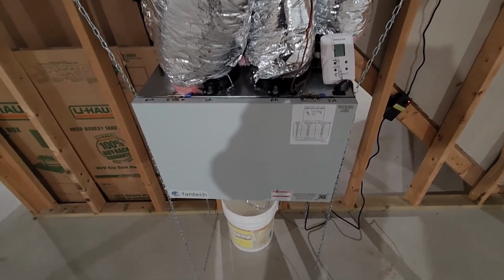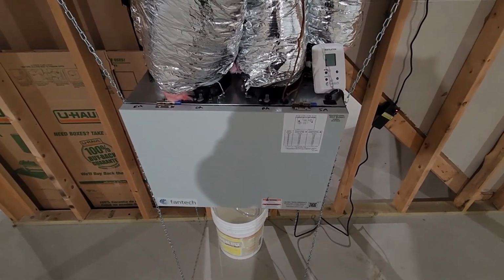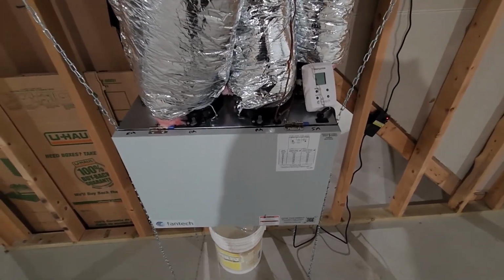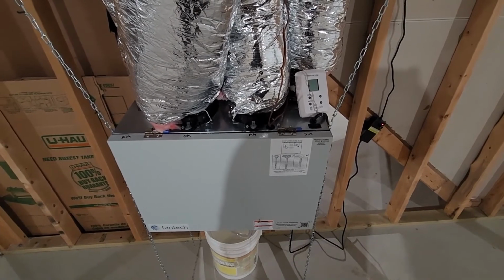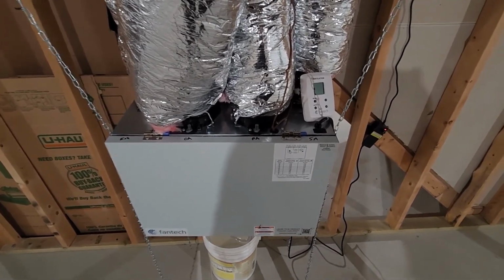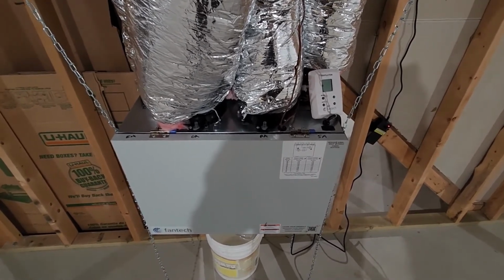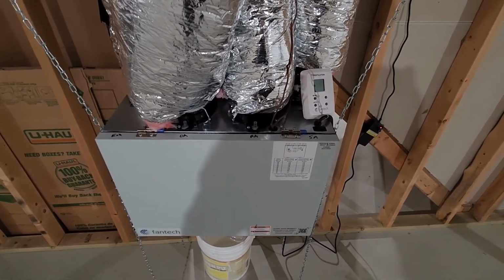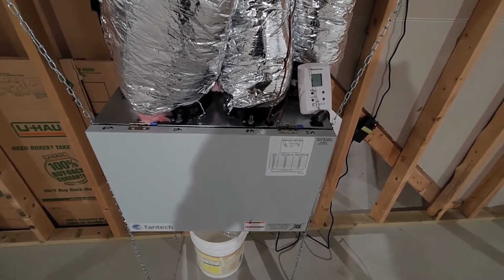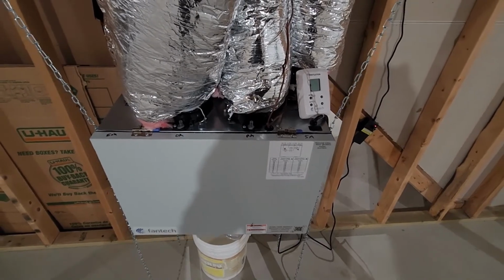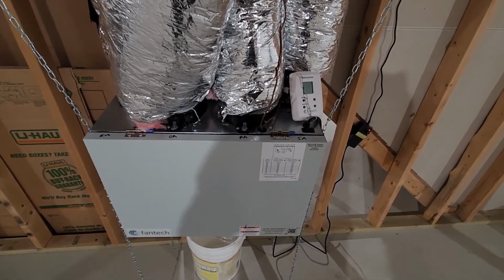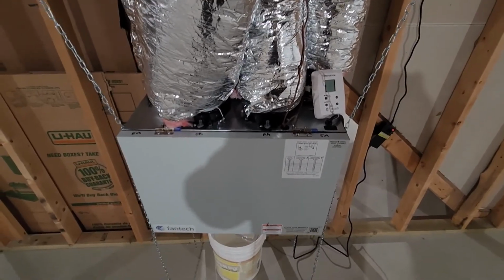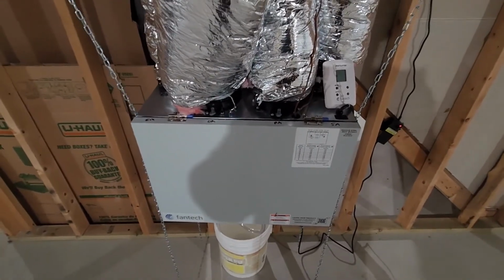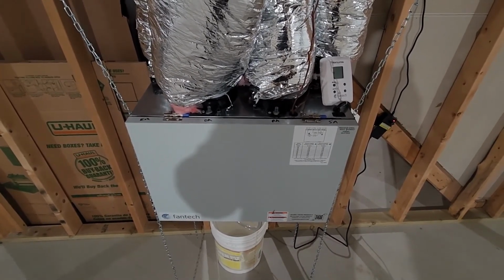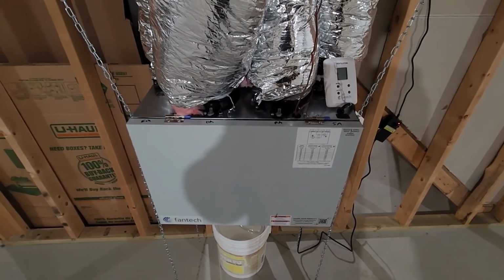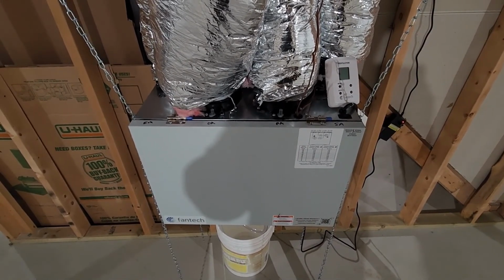with home pressurization issues, like your house being negatively pressurized too much, which could lead to infiltration air being brought in from the outdoors, and that would affect your heating or cooling bill. Or you could be bringing in gases like radon or methane from underneath your soil. And positively pressurizing, they claim, could lead to possibly pushing moisture into your walls or things like that. I don't really know whether that's feasible or not, but definitely didn't want to run into that. So I've got just barely positively pressurized leading balance to my system, like probably only 5 or 10 CFM positively pressurized.